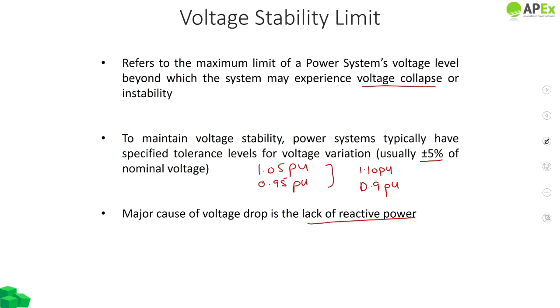Now, to understand the voltage stability limits, we take help of a curve called the PV curve. The PV curve, as apparent from its name, the power voltage curve, represents the relationship between the power transfer on a transmission line and the voltage at the receiving end substation. So let's say we have a generator connecting a grid station, and that power is transmitted through a transmission line to the load. As the load increases, at every step, let's say at 10 megawatt, it would show the power transmitted by the transmission line, which is 10 megawatt, and when the line is transmitting 10 megawatt, what would be the receiving end voltage of this grid station, right?